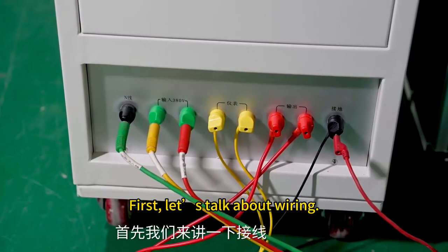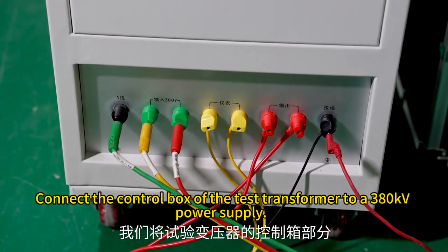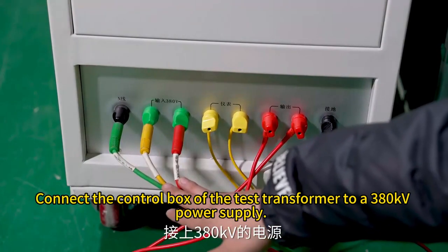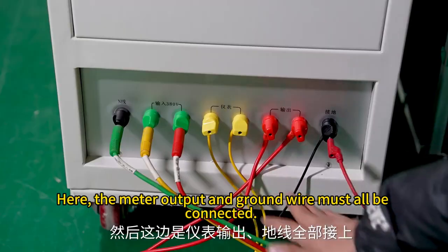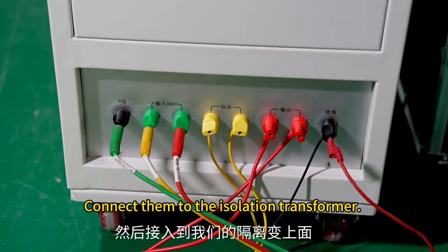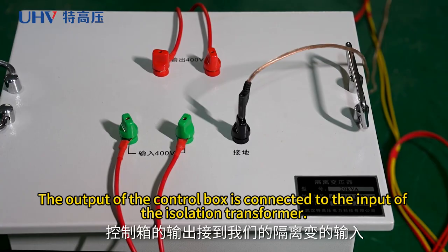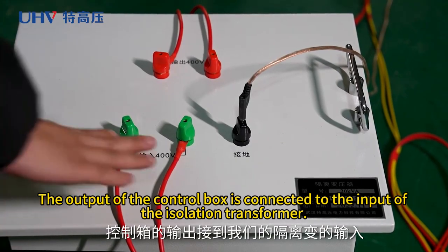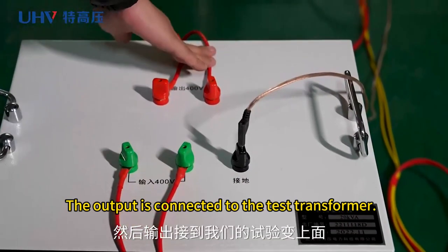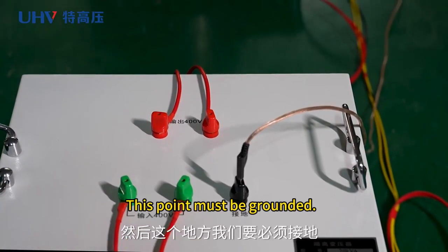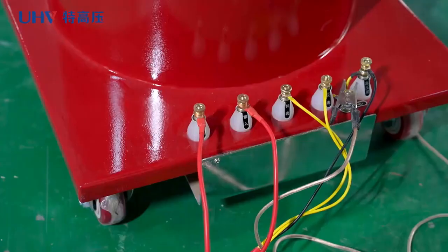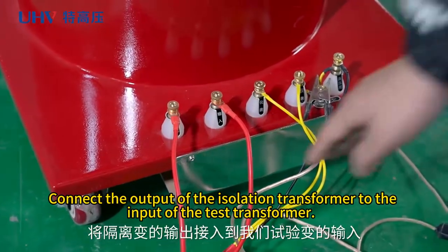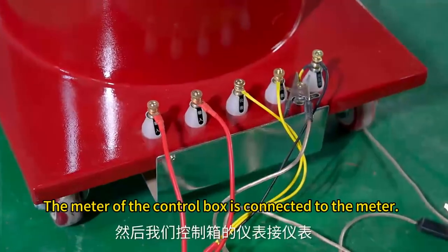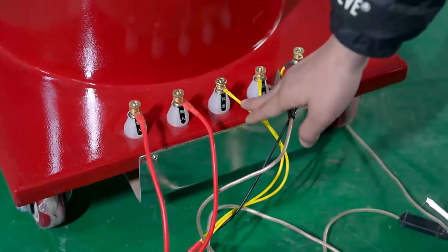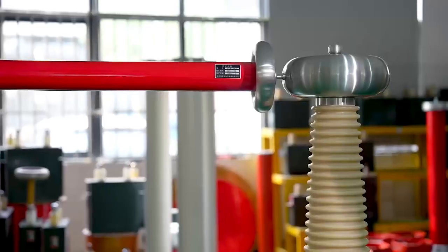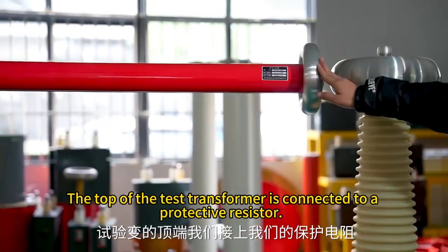First, let's talk about wiring. Connect the control box of the test transformer to a 380V power supply. Here, the meter output and ground wire must all be connected. Connect them to the isolation transformer. The output of the control box is connected to the input of the isolation transformer. The output is connected to the test transformer. This point must be grounded. Connect the output of the isolation transformer to the input of the test transformer. The meter of the control box is connected to the meter. This point is grounded.